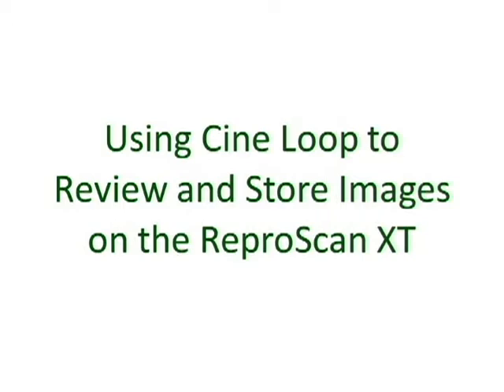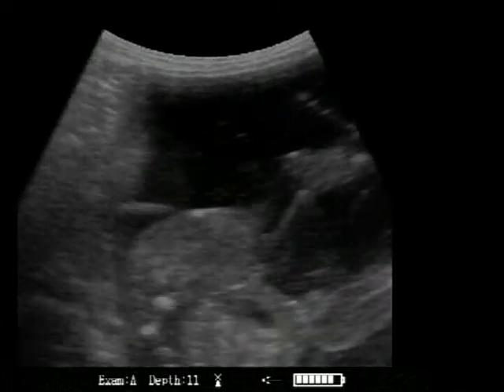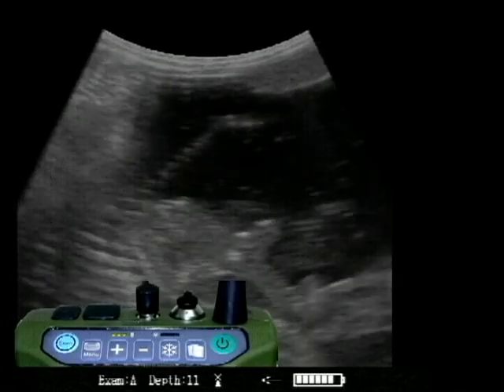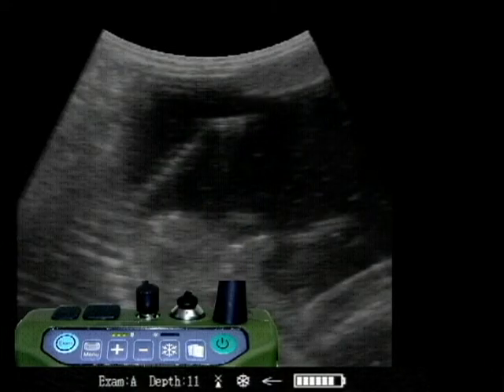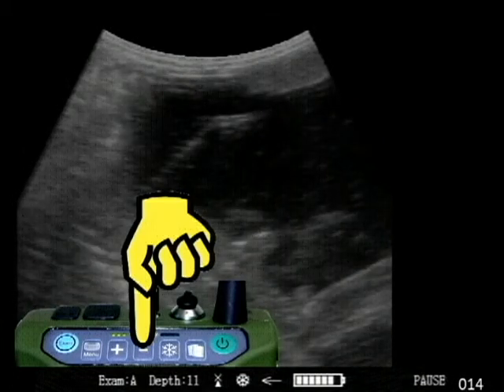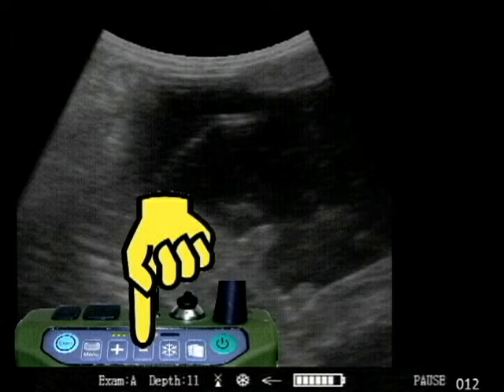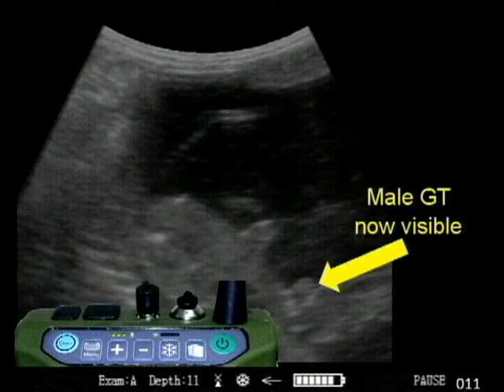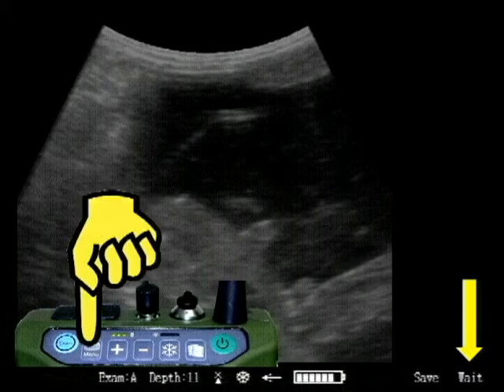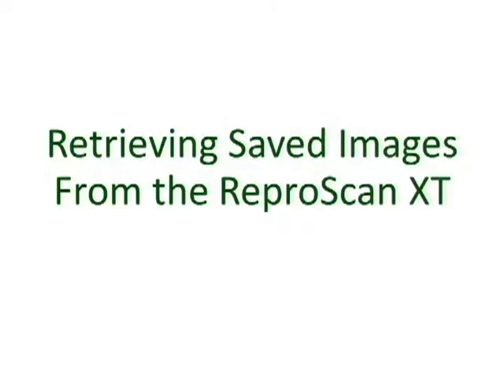Now we're going to look at using the CineLoop feature to retrieve and store images on the ReproScan XT. Let's see how the CineLoop feature can let us do a better job of freezing and storing images. Freeze there — we've missed the male genitalia. Press the CineLoop feature, then use the minus button to scroll back until we get a better image. There's the male genitalia now visible. Press CineLoop, then plus, then menu to store that.